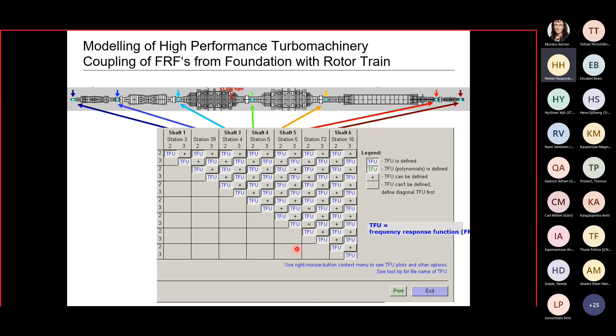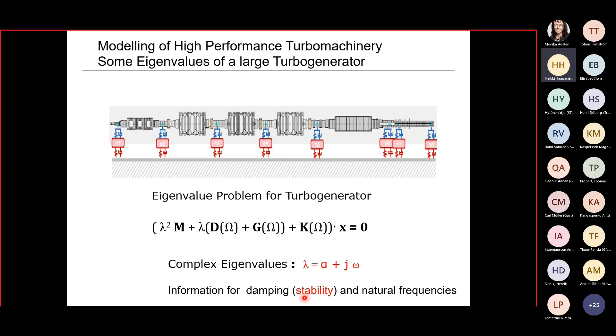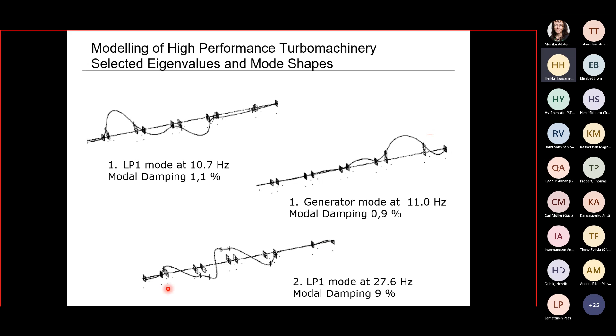Now, when we have all this done and we have built up the model with all effects, then we can calculate, of course, different things. For example, the eigenvalue problem for such a turbo generator leads to the eigenvalues expressing the damping behavior and the natural frequencies. There's also information available regarding the stability. Here are some examples for the mode shapes for a large machine. So there is 10.7 Hertz with a corresponding damping. It's mainly in this low pressure part. Then we have another typical generator, first bending at 11 Hertz with the special damping. And here's a higher mode at 27.6 Hertz.